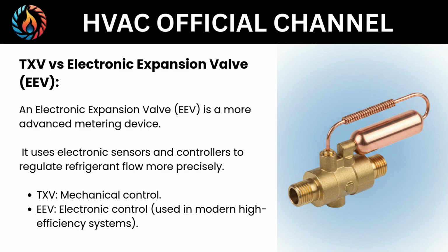TXV versus Electronic Expansion Valve, EEV. An electronic expansion valve, EEV, is a more advanced metering device. It uses electronic sensors and controllers to regulate refrigerant flow more precisely. TXV, mechanical control. EEV, electronic control, used in modern high-efficiency systems.